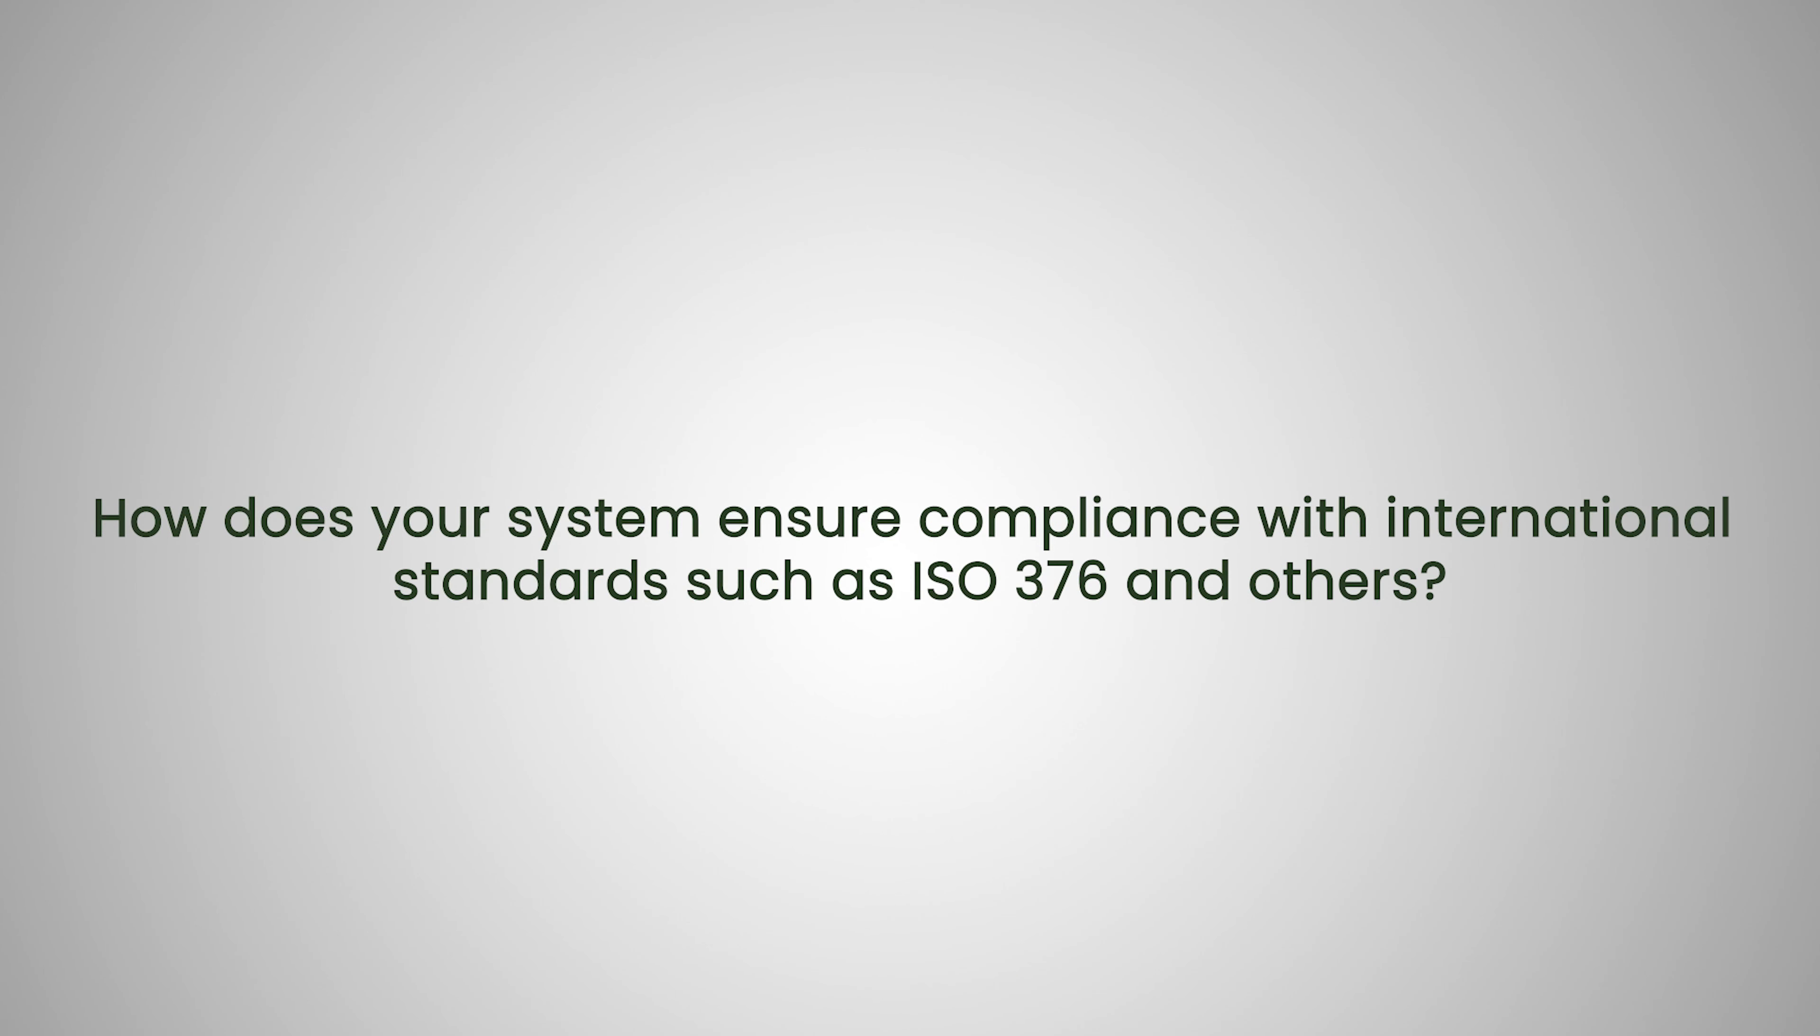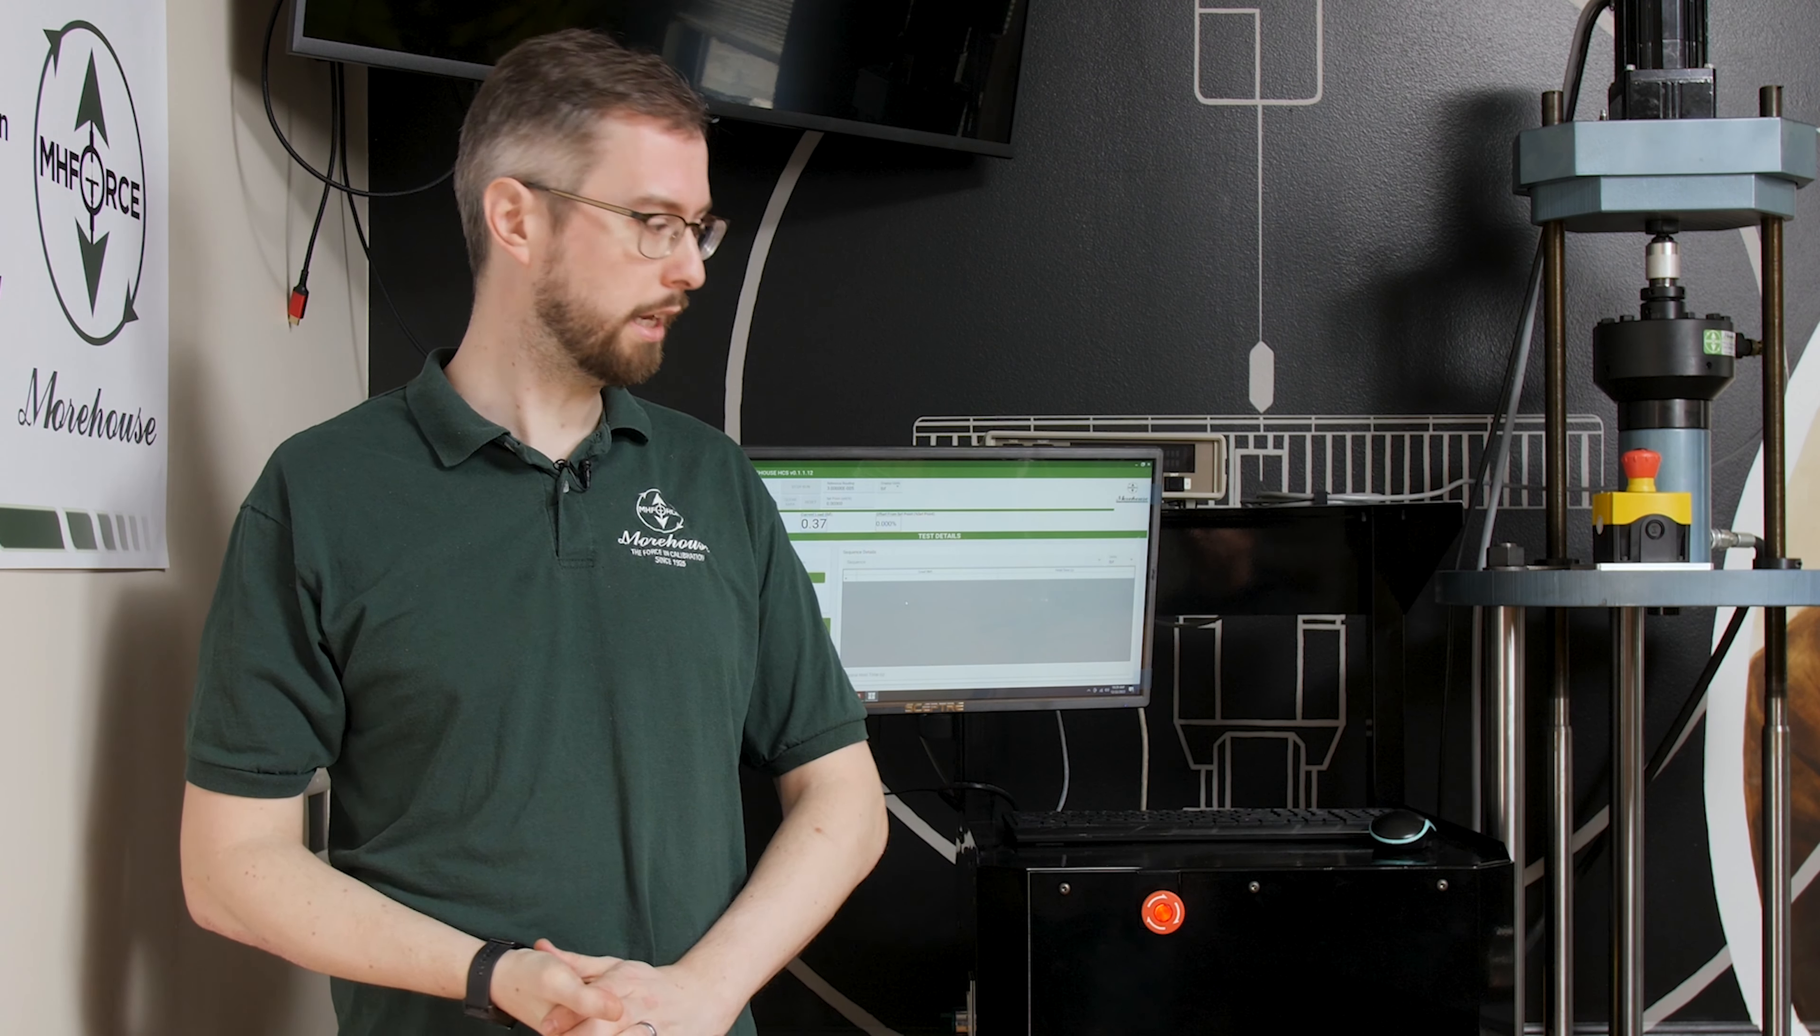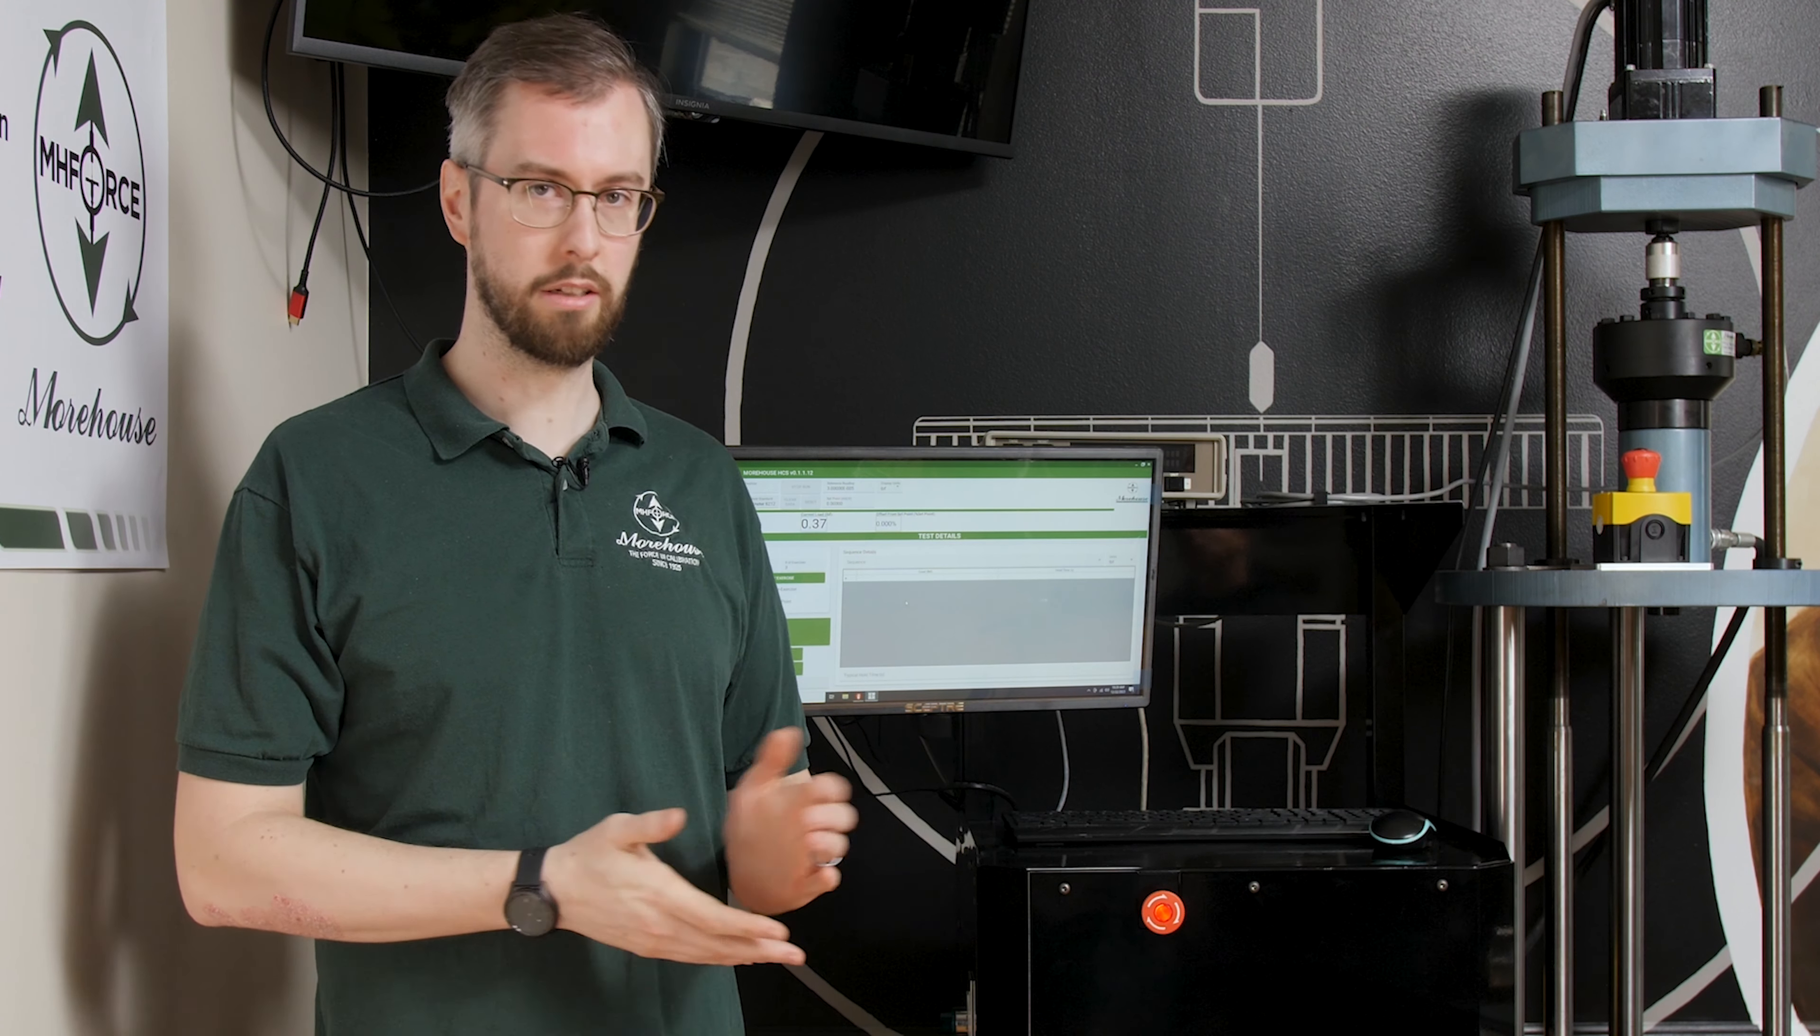How does your system ensure compliance with international standards such as ISO 376 and others? So you can configure the system to wait a certain amount of time before taking a reading. So that allows you to comply with ISO 376, which requires that you wait 30 seconds before taking a reading. And then you can also, ISO also has a creep test requirement for certain cases. So you can wait until you get back down to zero and take a reading at 30 seconds and then 300.